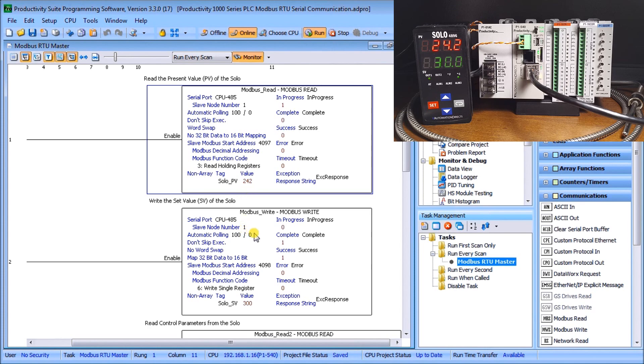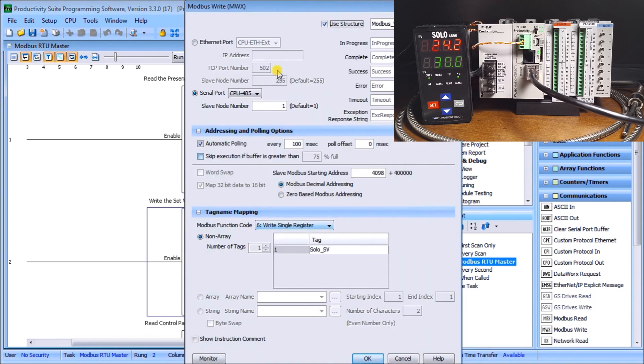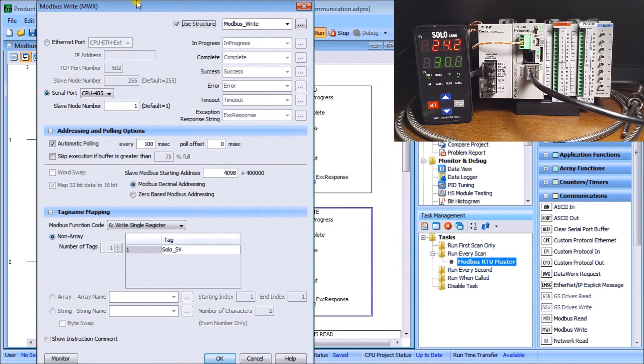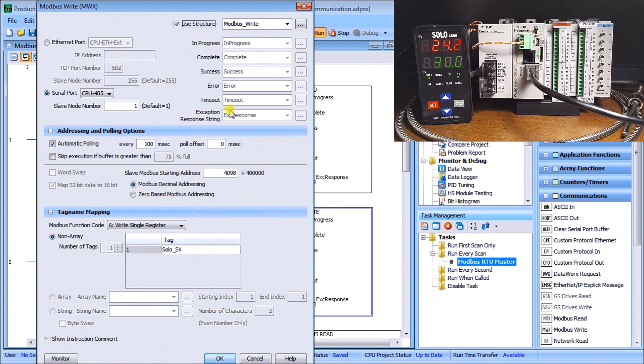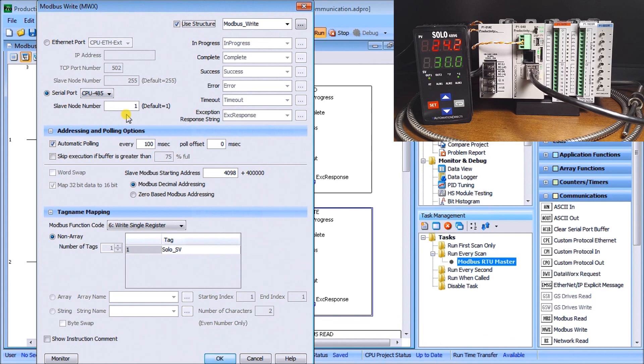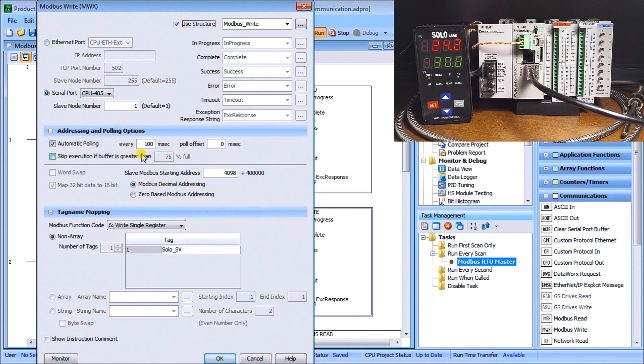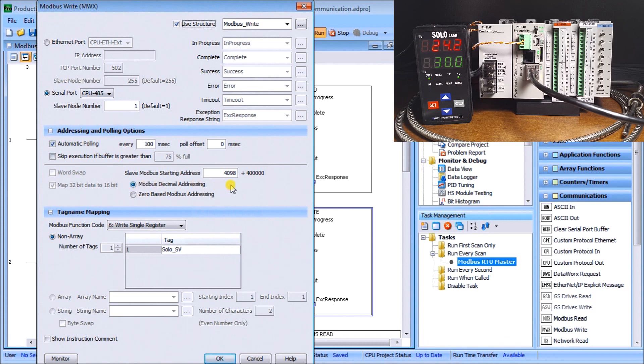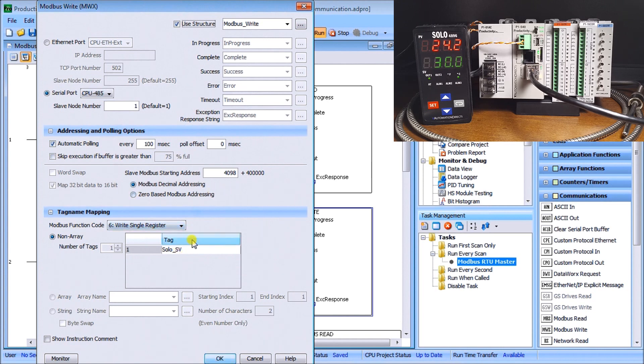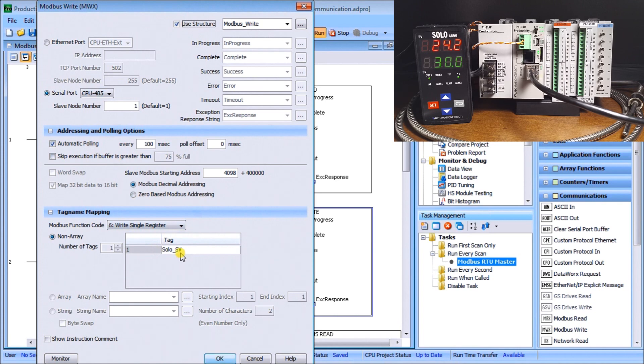The next instruction is my write instruction. On my write instruction it's very similar to the previous read. I'm using structure again so modbus write and we set up these flags for us. We have set for our 485 serial with node number one so it means that we're talking to our solo. Again we set up the automatic polling set for every 100 milliseconds. Our modbus decimal addressing and this time our slave starting address will be 4098 which is actually our solo set value. This is a set value that if we put into the unit we'll actually set our solo to that value.